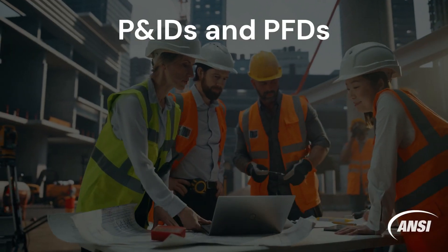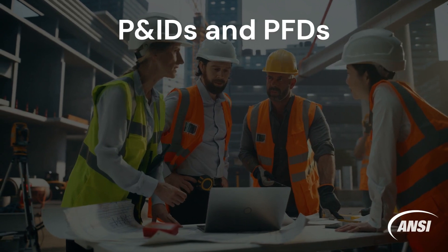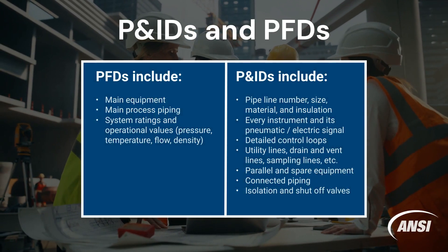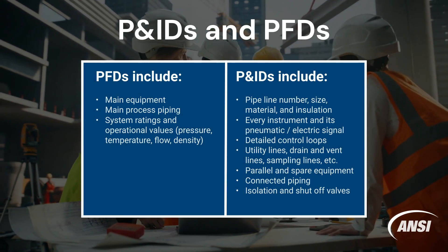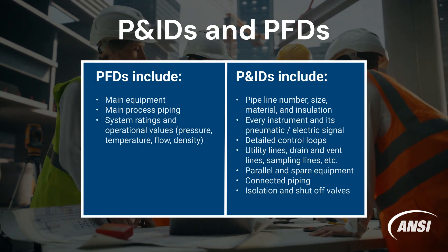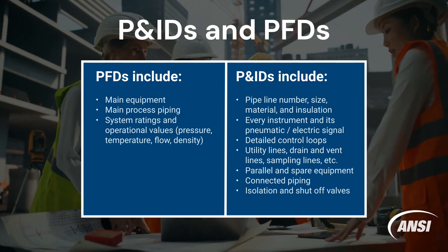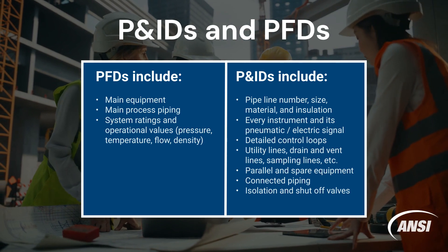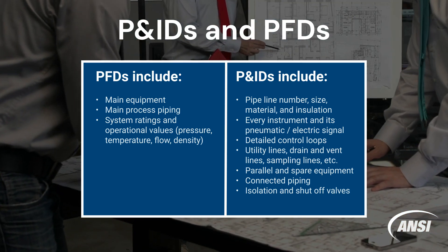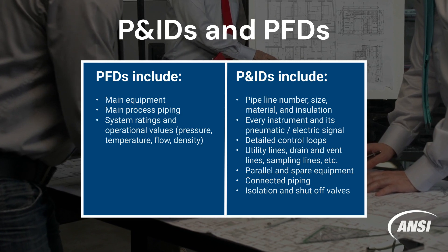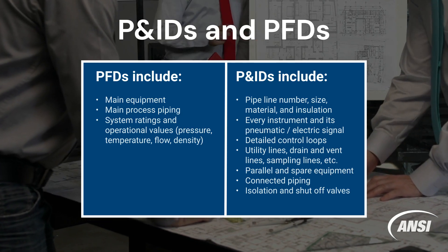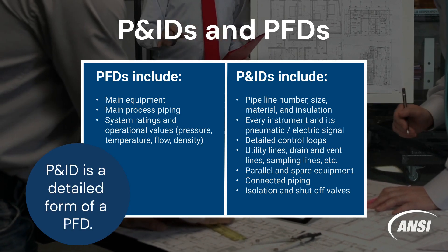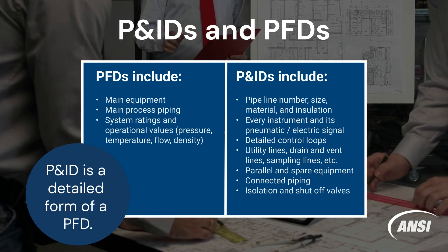Piping and instrumentation diagrams can often be confused with process flow diagrams. A process flow diagram shows the connectivity and relationships between the main equipment and units of a process, while a piping and instrumentation diagram typically includes more information about piping, controllers and valves. Additionally, piping and instrumentation diagrams do not contain operational specifications that process flow diagrams do, such as flows and stream compositions. Essentially, a process flow diagram is a simplified version of a piping and instrumentation diagram.